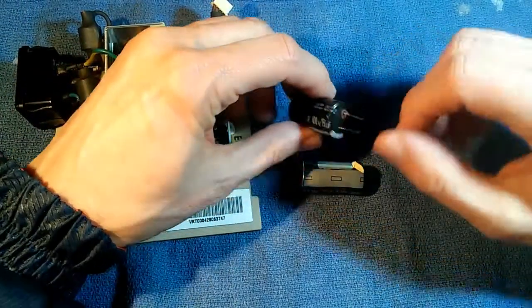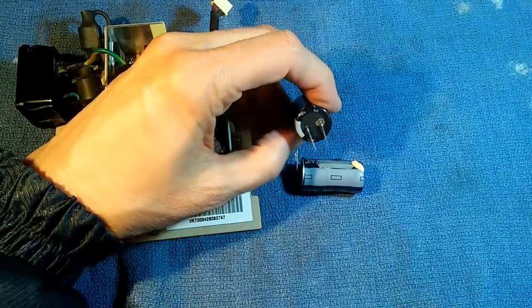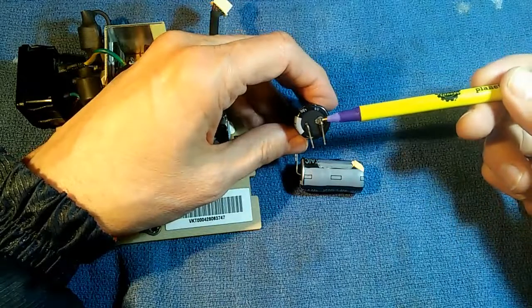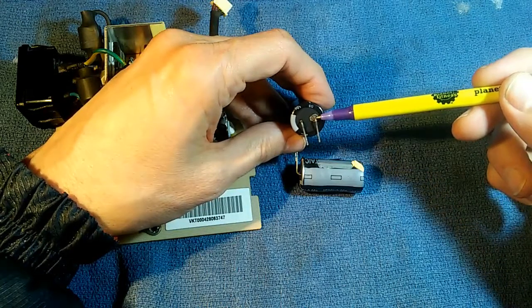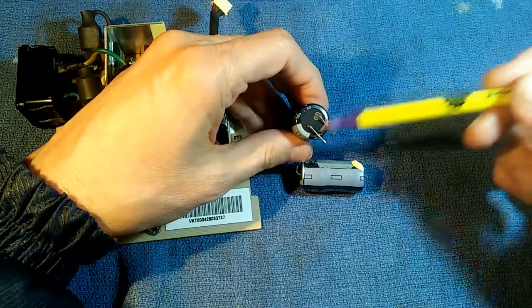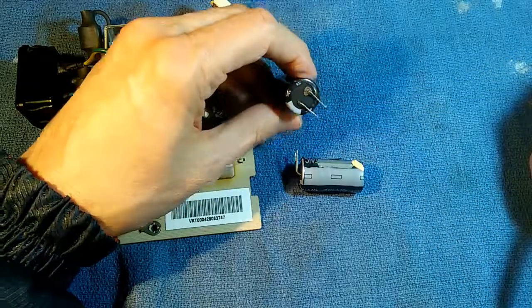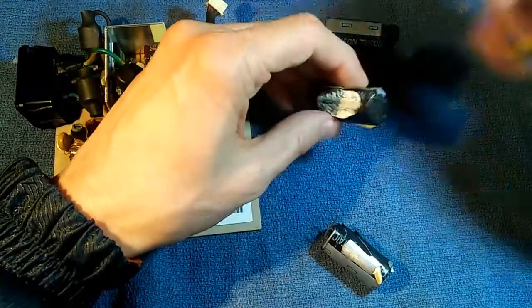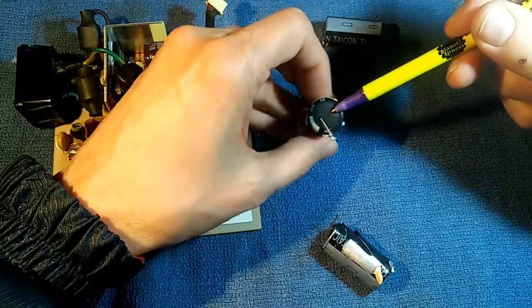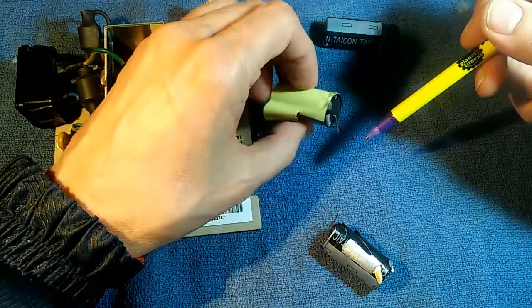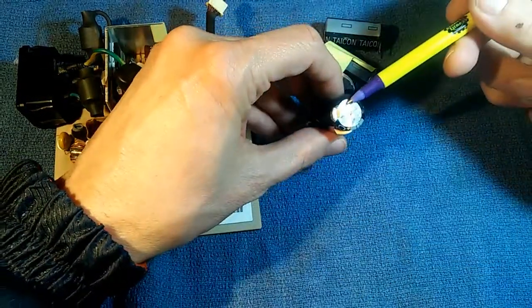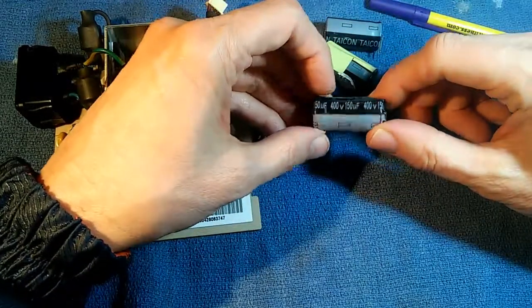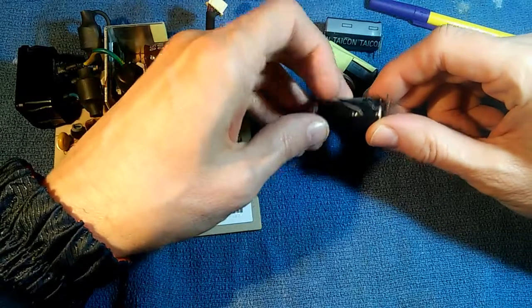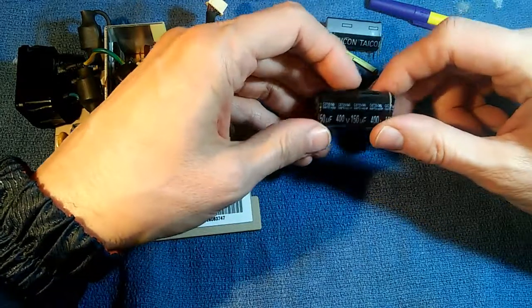They'll have this brand name on them, Taicon, and they fail with an atrociously high frequency. Sometimes they'll basically look normal, but if you look at the end, you'll see this material dripping out of the terminal. If you check it with a capacitance meter, it'll read zero. Here's another one - oftentimes that pin will just literally fall out. Here's one that's actually swollen. And this one got so overheated that the plastic actually started peeling and falling off.